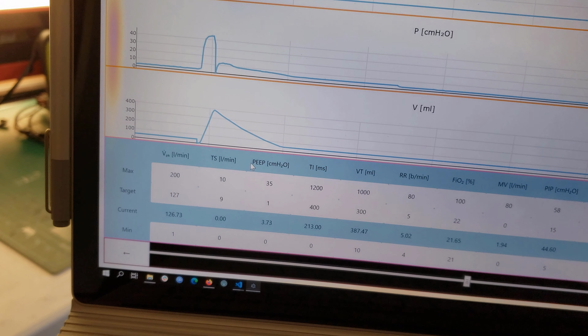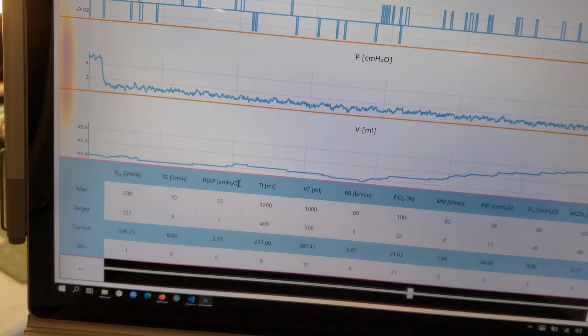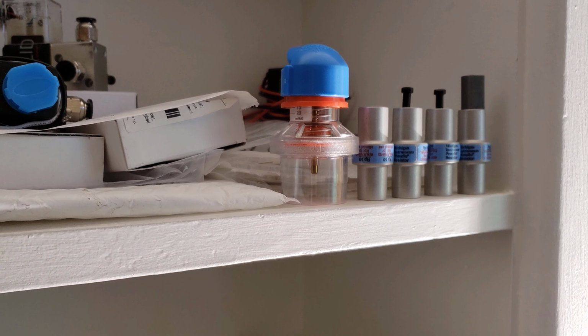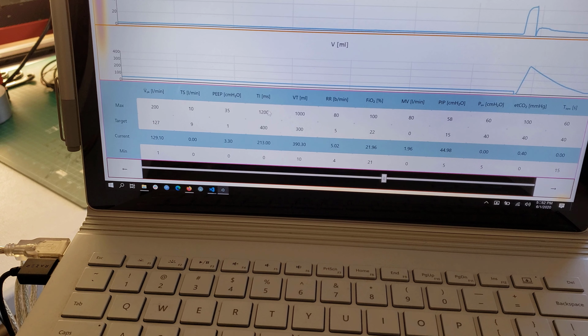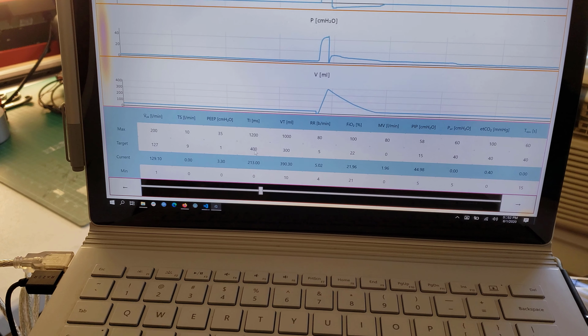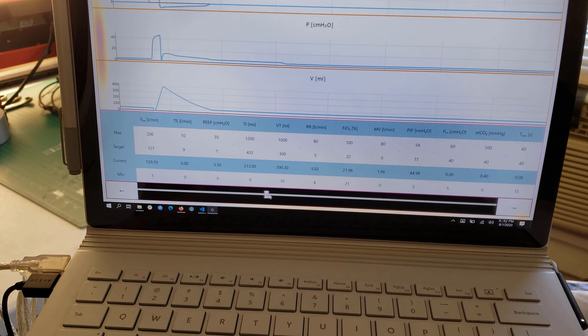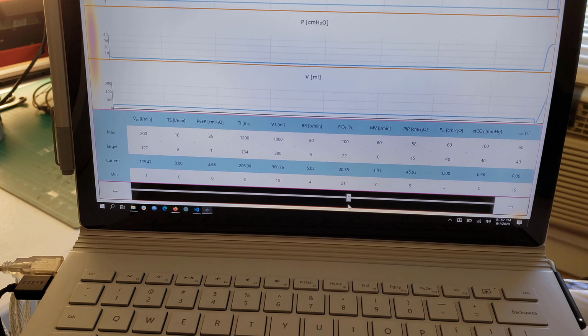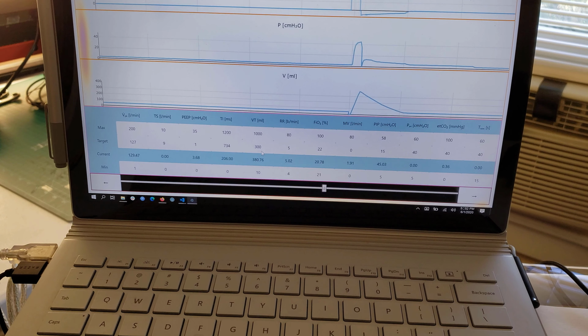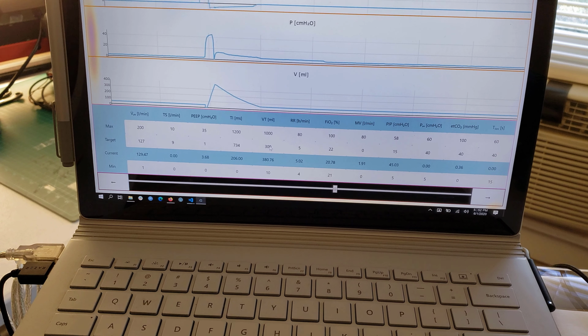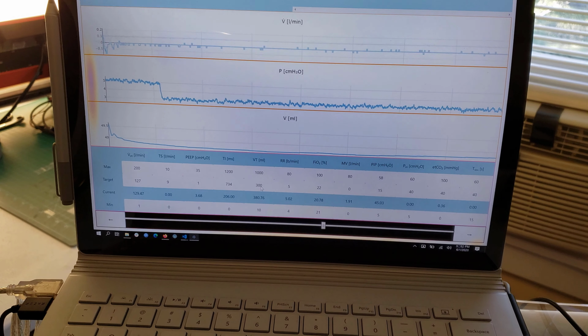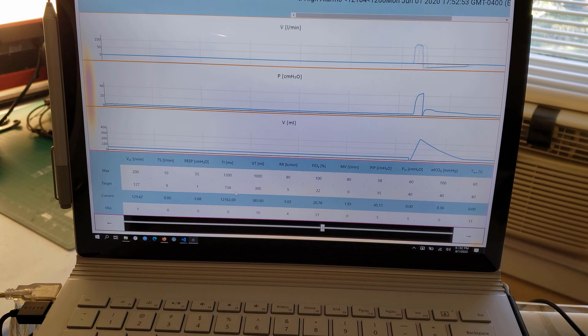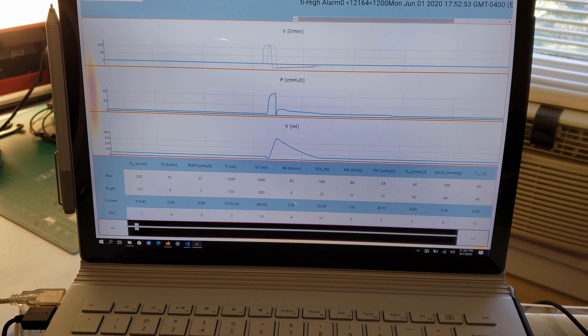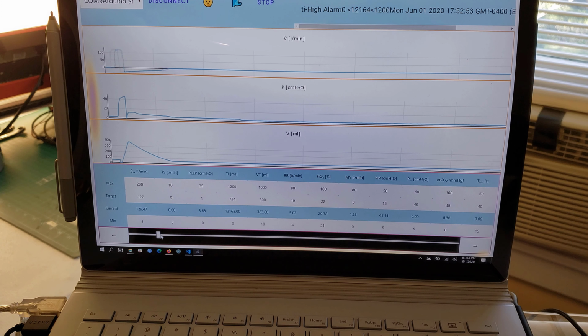Here we have PEEP. This we can't control internally, but you can do it with an external PEEP valve, like this one over here. I can increase the inspiration time, but it won't really change until we also increase the tidal volume. The inspiration time can be decreased to more precisely control the tidal volume. I think I'll skip the respiration rate and come back to tidal volume because this is way too slow. A couple of these alarms will sometimes trigger during initial changes to the target fields, but after a couple breaths they'll stabilize and won't trigger again unless something is actually going wrong.